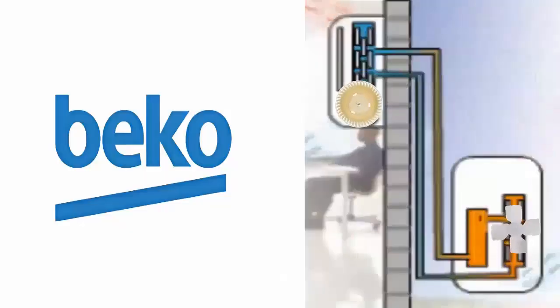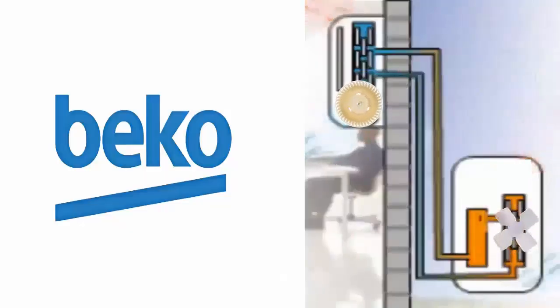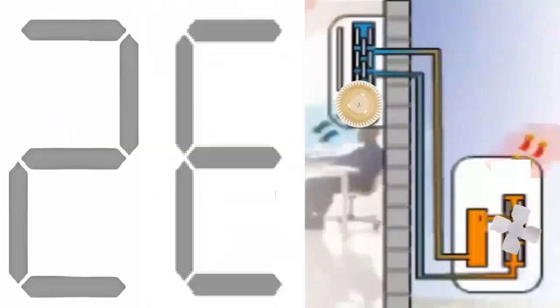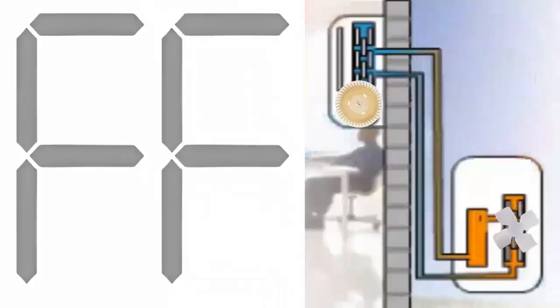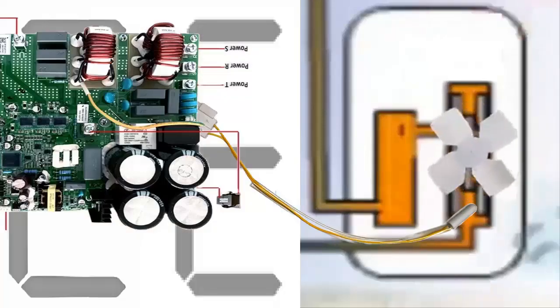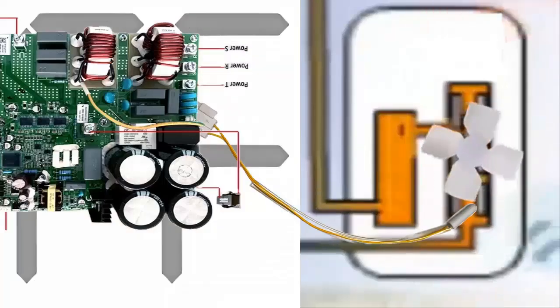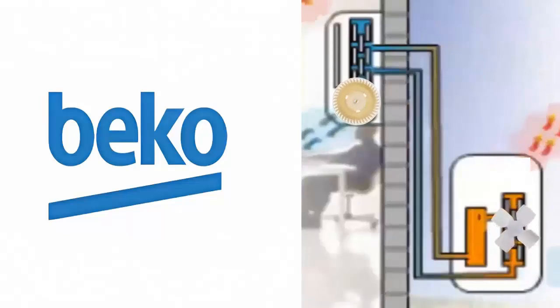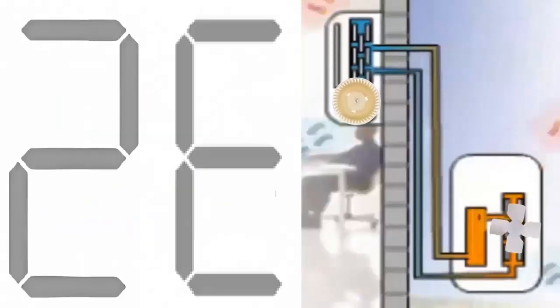Error code E2 or FF09 is associated with issues in the sensor located in the outdoor unit, adjacent to the external heat exchanger piping. This sensor measures the refrigerant temperature during the phase change to calculate the refrigerant saturation pressure.